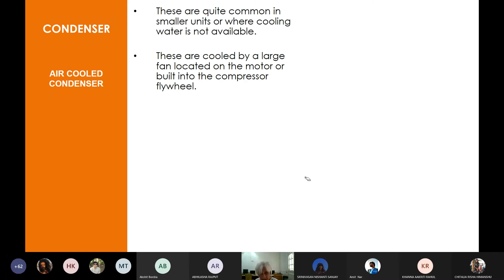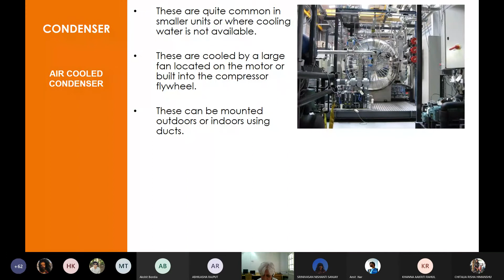Okay, so look at the size of the condenser. It is equivalent to what your compressor was. Pretty big. Okay, it's huge. These are quite common in smaller units. Okay, air cool wala. We are talking about air cooled condenser. These are cooled by a large fan located on a motor or built with a. So this large thing that you see is actually a fan. Into the compressor flywheel, and this can be mounted outdoors or indoors.